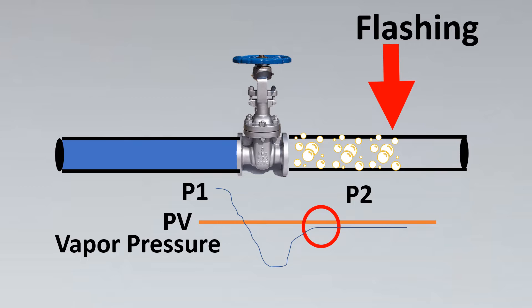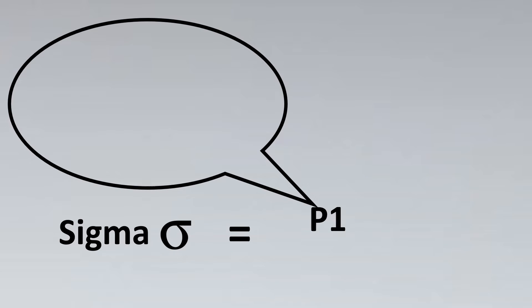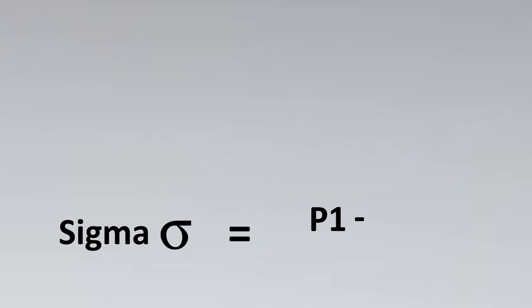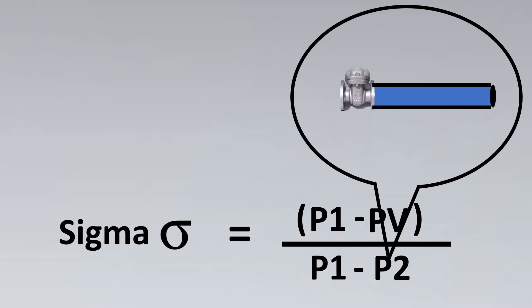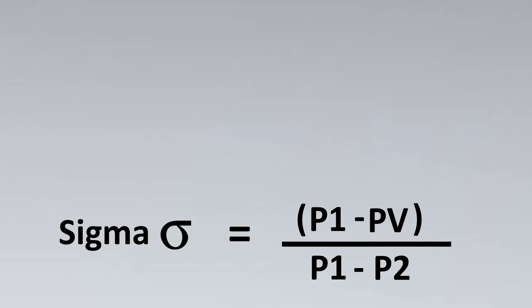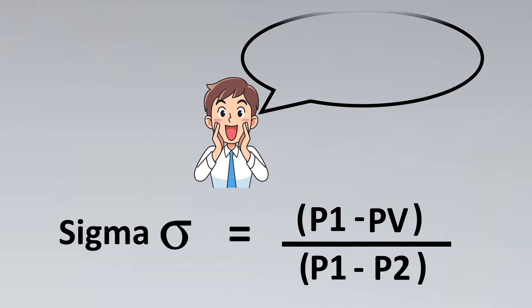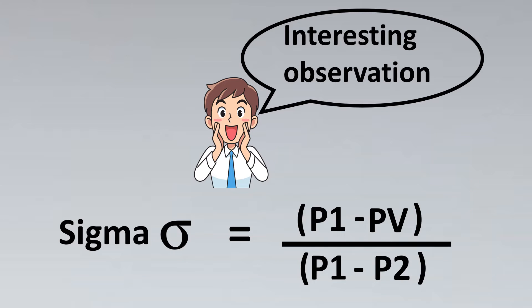Now let's get to this term. Cavitation index, which is also called sigma, is defined by ISA as follows: it is P1 (pressure upstream) minus PV (the vapor pressure) upon the pressure upstream minus the pressure downstream. This is the sigma value.